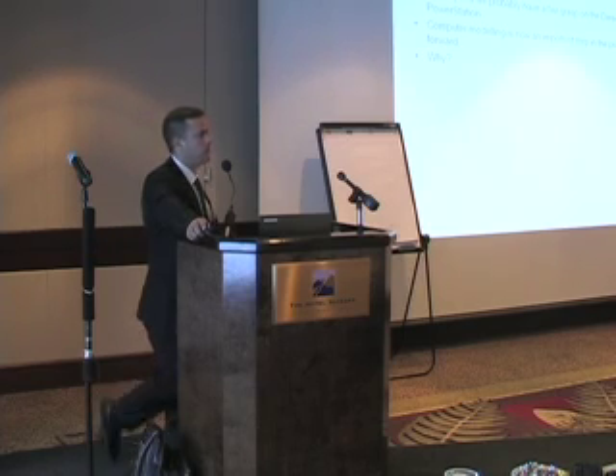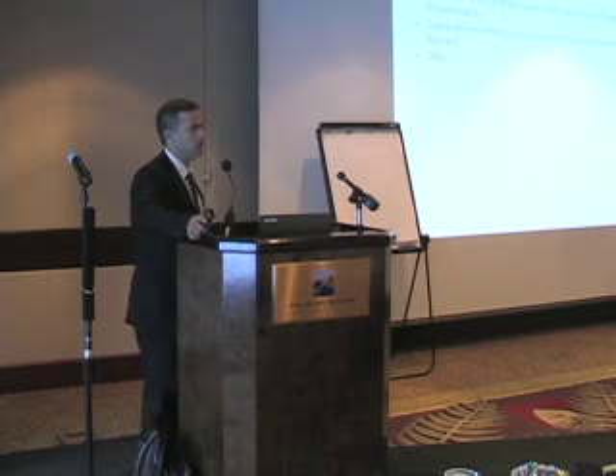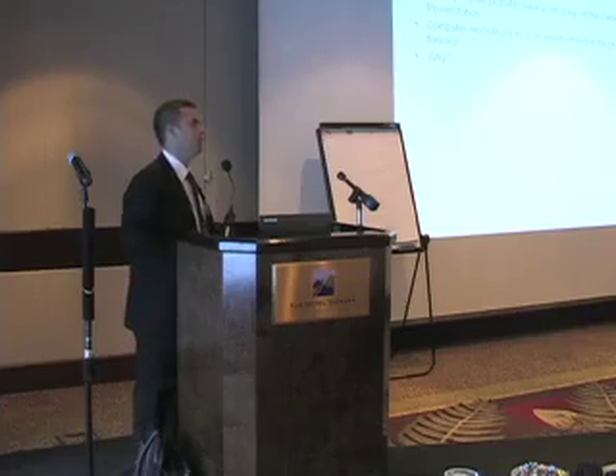Do they run aerial earths generally for that reason? Sorry? Would you run an aerial earth around the system? Well, you just need to know what the ground resistance is. If you're putting in a substation and you have some options where you put it, you want to put it where ground resistance is lower, so you get higher fault currents. Or sometimes you have to run a ground grid to get the resistance low enough.